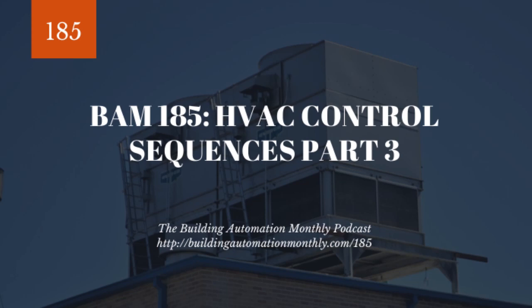So occupied operation will be determined via several different things: an occupancy schedule, forced occupancy override, push button override on the space sensor, an external scheduling device, etc., etc. And what we're going to do here is we typically will have three kinds of modes as far as occupancy goes. We'll have unoccupied, occupied, and off. And there's an important reason we have off. If you are doing maintenance, sometimes you call it maintenance, you don't want to have it in unoccupied. You want to have it off. And that's really important because of unacknowledged alarms and all sorts of effects it may have on other sequences.